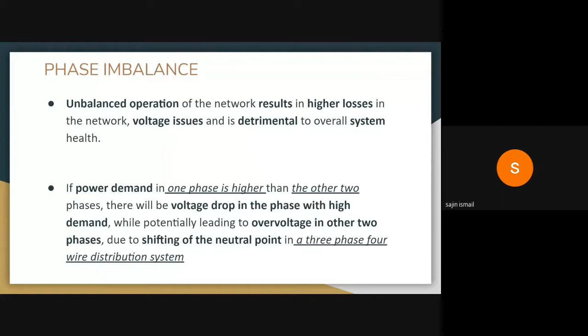Shifting of the neutral point may occur if the chargers are not properly distributed among the phases of a distribution transformer in a distribution network. This is a very important issue to take care of as the number of electric vehicles increases in the market. The distribution of chargers should be careful, since a single phase charger of 3.3 kW minimum will be rated.